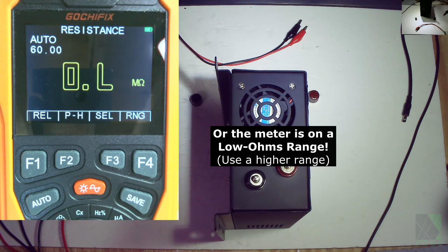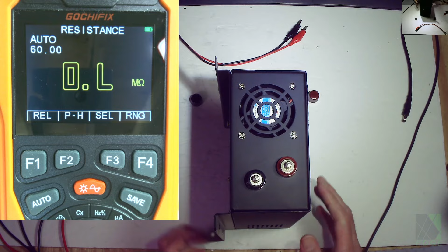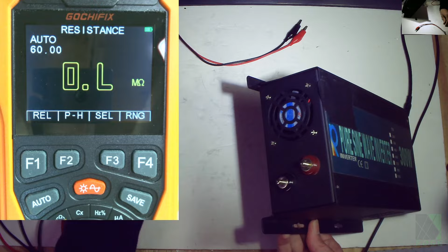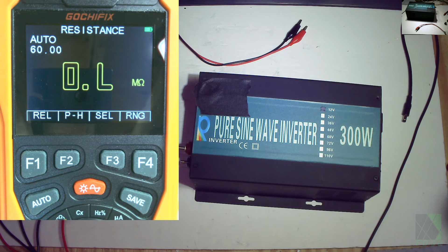What does that tell us about the inverter if it just says open circuit on the meter when I probe these two connections? What it's telling you is that something has gone wrong inside the inverter because it should not be open circuit. More than likely what's happened at the very least is the fuses, which are often placed inside these types of inverters, have actually been blown. Now, not all inverters are built the same. They're all different. This is just an example of one. And they may have fuses inside that you can't see.